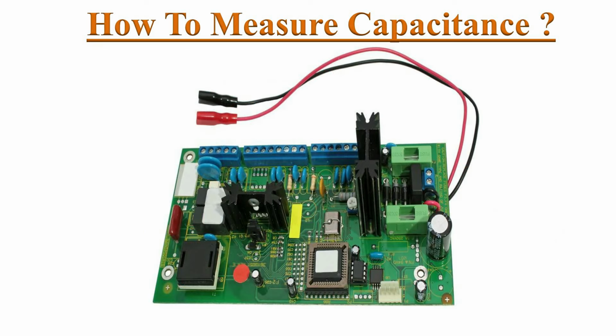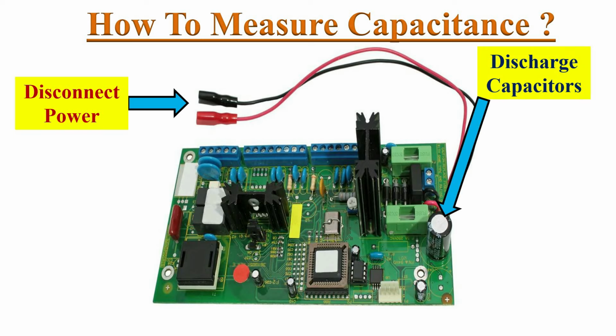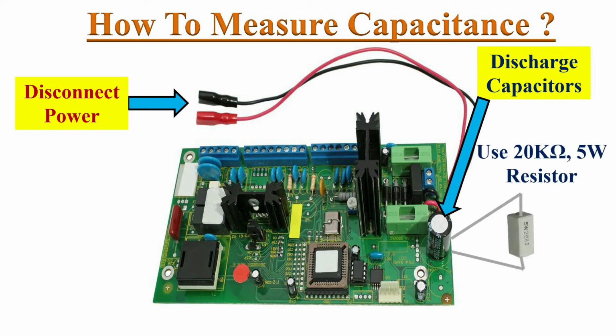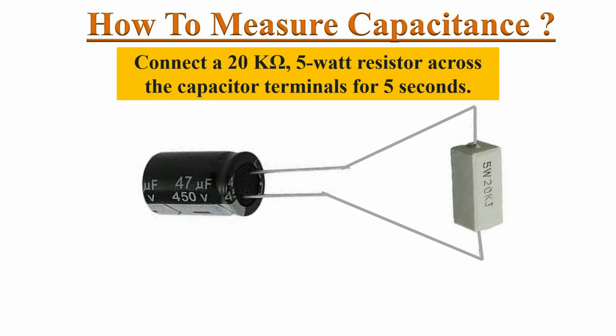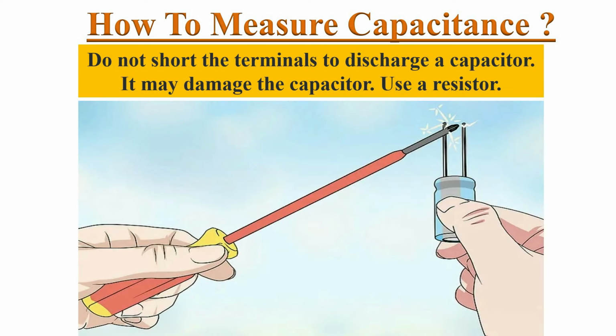Before measuring capacitance on the circuit, ensure that power is disconnected to the circuit and discharge the capacitors by connecting a 20 kilo ohm 5 watt resistor across the capacitor's 2 terminals. We need to connect the resistor at least 5 seconds across the capacitor's 2 terminals in order to completely discharge the capacitor. Do not short the capacitor's terminals using a screwdriver or with any other metal to discharge the capacitor, as it may damage the capacitor.